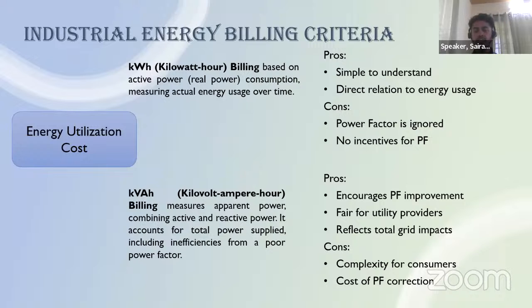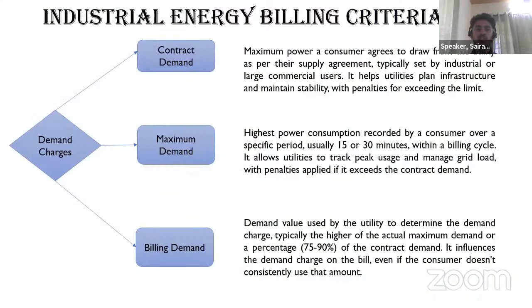The setback or con of kVAH billing is that it is somewhat difficult for non-technical persons to understand how the billing has been made. And also, if you are maintaining the power factor at a very poor state at your user end, then you have to install power factor correction measures that will require some cost. Even if you invest that amount for power factor correction, you will get that amount compensated in terms of kVAH billing. The demand will be drastically reduced and you will get the benefit instantly. And with that, the energy utilization charges are completed.